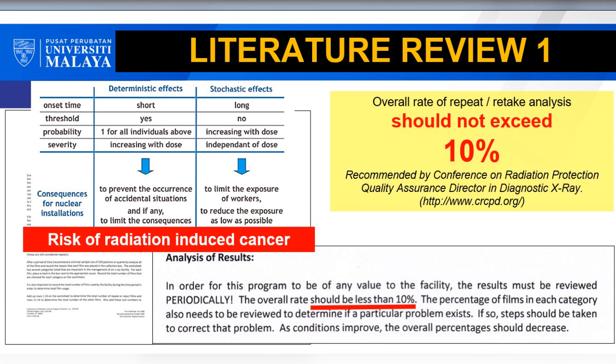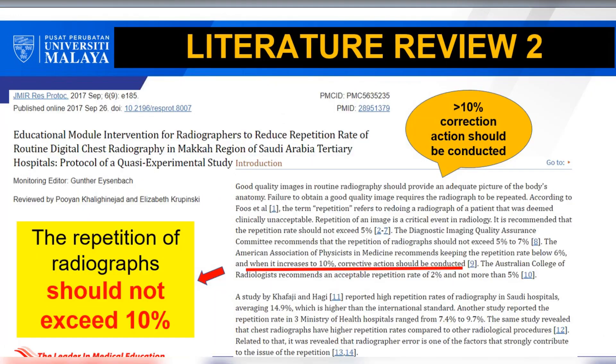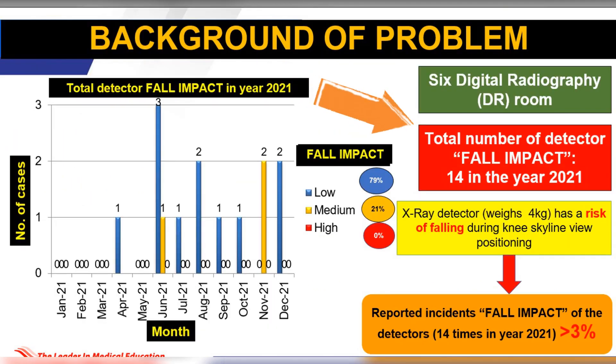In addition, the repeat X-ray could increase the risk of radiation-induced cancer. Therefore, corrective action should be conducted when the retake rate exceeds more than 10%. There were 14 incidents of detector fall reported in 2021.